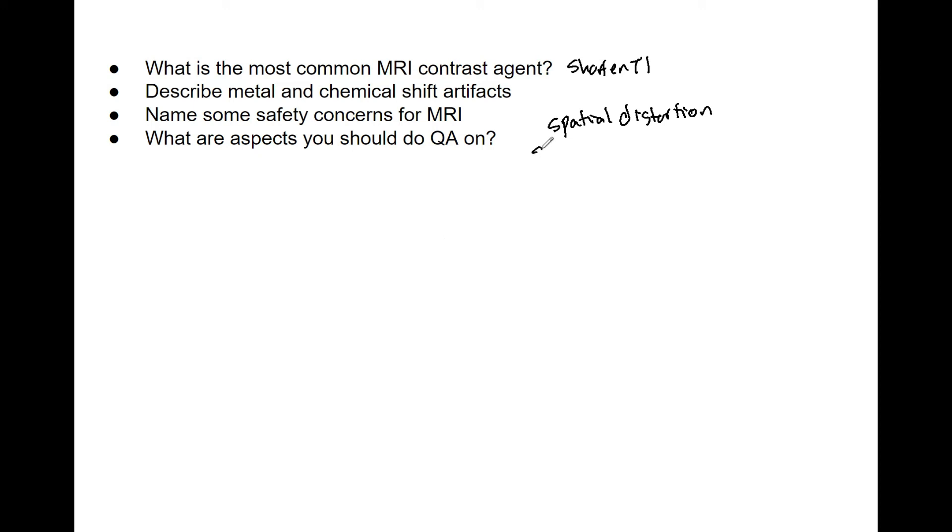You also want to look at your signal to noise ratio, then verify your magnetic field strength and field homogeneity. You want to ensure that the entire magnetic field is the same strength throughout. You have gradient linearity you want to ensure is correct, and then finally, your RF tuning.